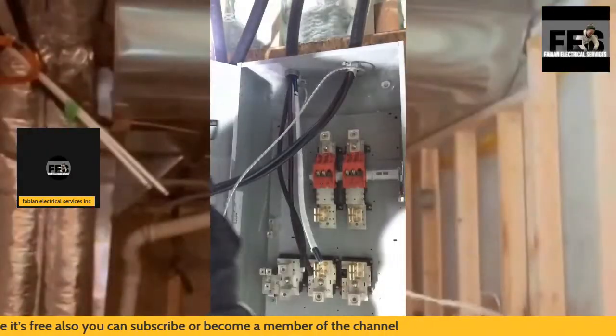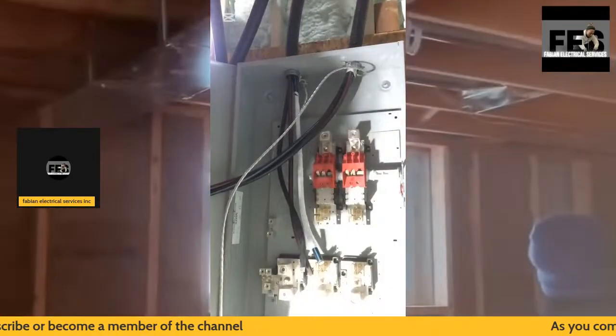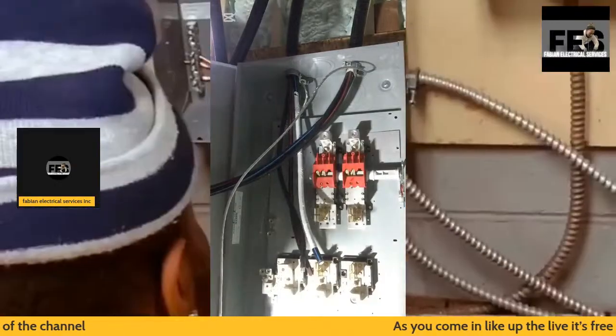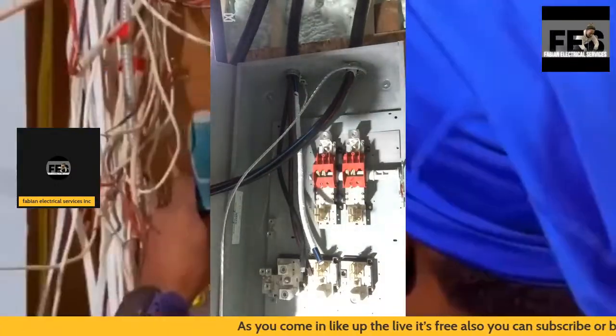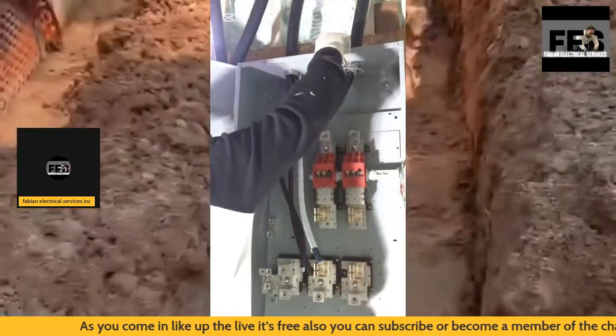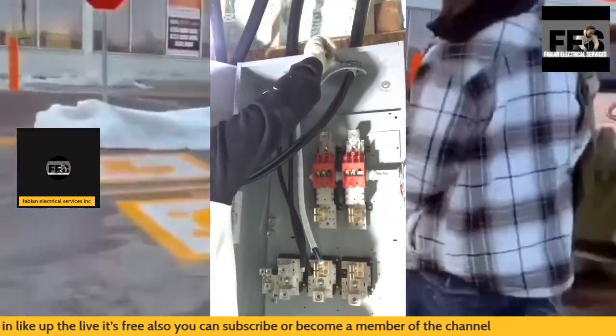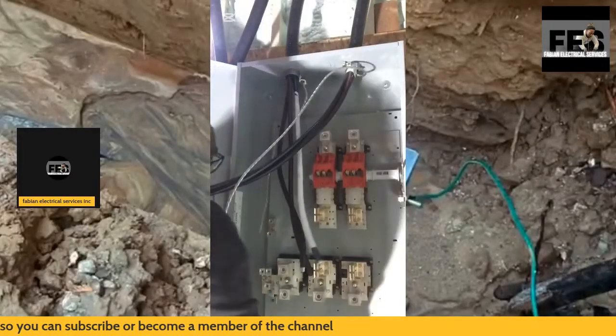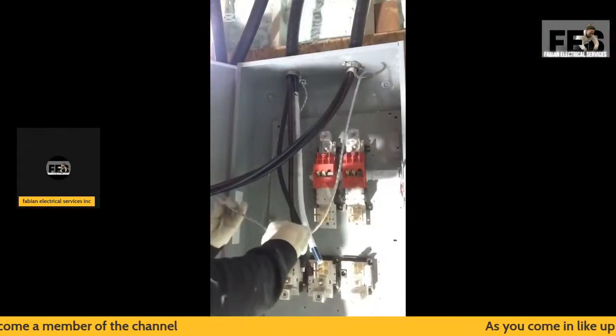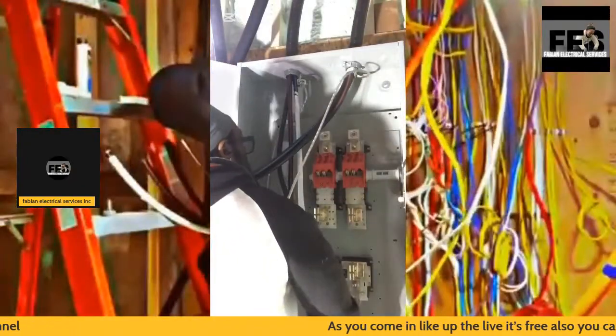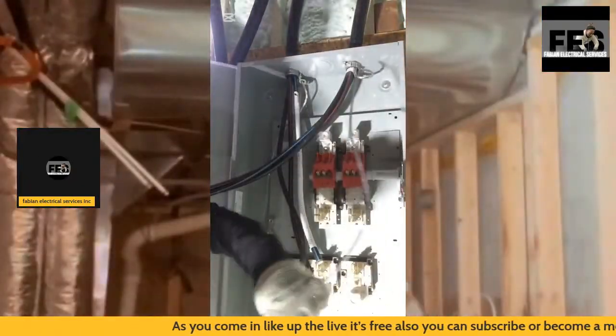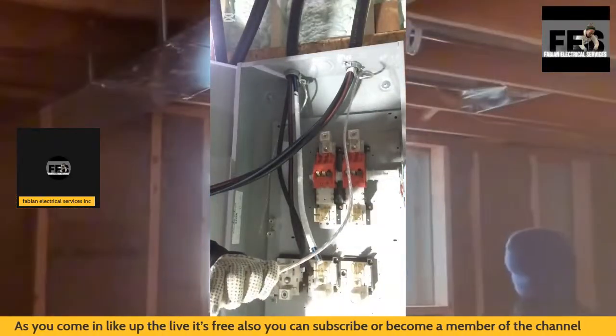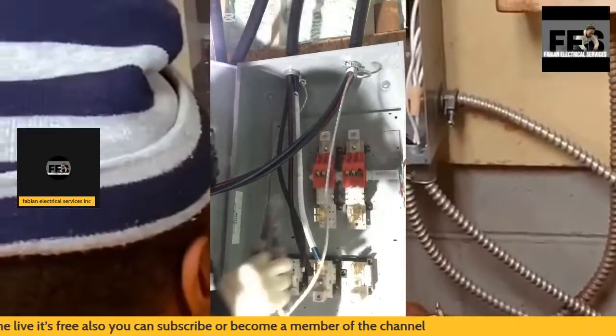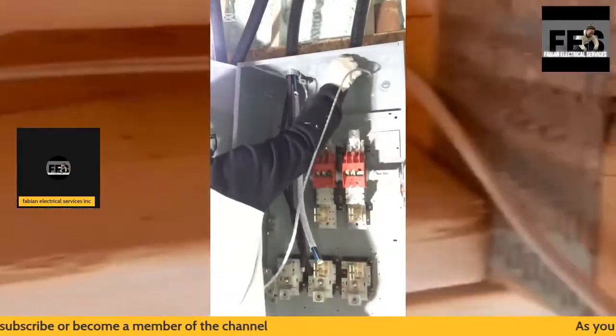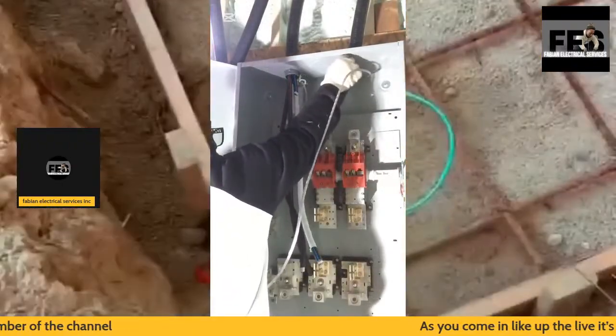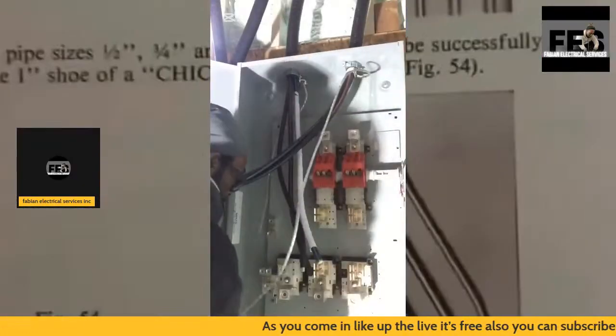As you can see, the reason I like to keep the white paper on is it simply helps with the cable. The cable is locked in place. Once you disassemble that, it gives you a lot more problems getting the cable inside of the connector. So that's why I always make sure I land my cables inside of the connectors of the disconnect, and then I remove that. Then I go ahead and ground off my ground. I do my groundings. So this is a grounding and bonding installation. There are two different things when it comes to bonding and grounding. They serve two different applications, so never get that confused.